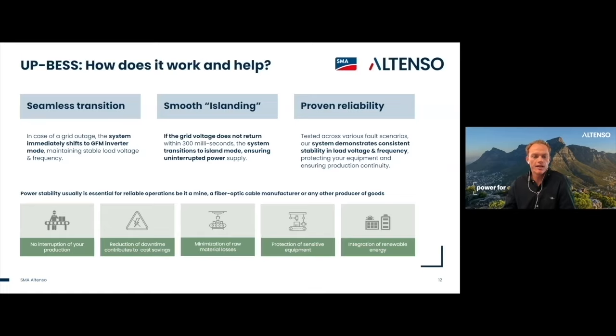And then if the grid doesn't return within 300 milliseconds, the system will then smoothly island itself and run off the battery capacity until the grid returns, or if needed, until the gensets start up. So this solution wouldn't only be relevant to the mining sector, but also other industrial customers running sensitive loads, such as manufacturers, data centers, agri-processors, and others.